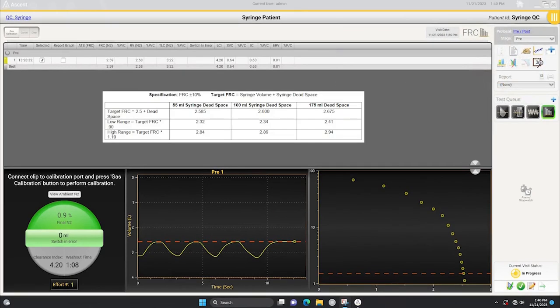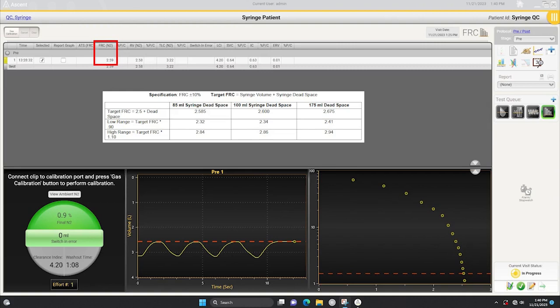After the effort has ended, verify that the measured FRC value is within the target range in the table shown. Depending on your model of syringe, locate the appropriate syringe dead space column, then note the lower and upper range for FRC. Your measured value should fall within that range.